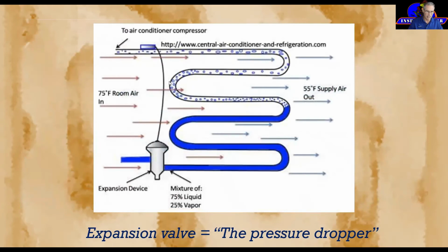This depicts that whole process much better. It comes out as mostly liquid, not pure liquid, and converts into that vapor again as it goes through the coil. One thing, while I'm thinking of it, look at these temperature probes. When you're looking inside the unit, you want to make sure that those are actually secured. If they're not, the whole process doesn't work right.